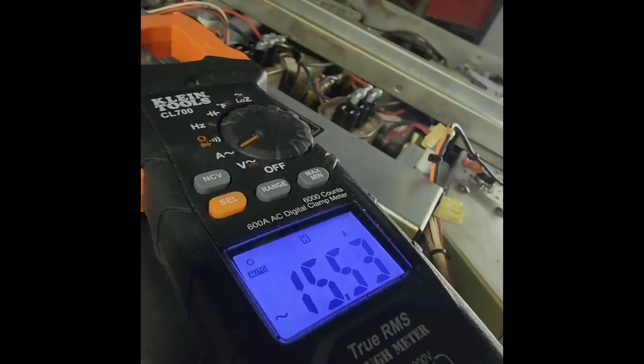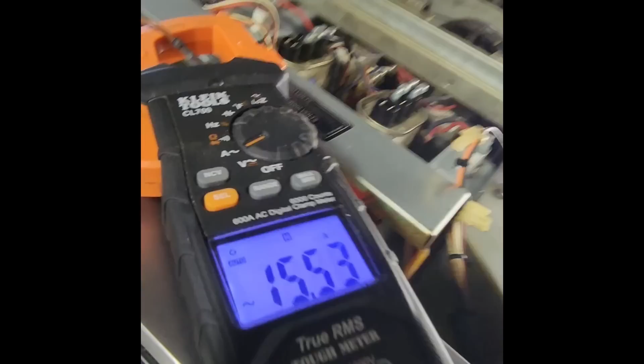Again, I'm doing another cook cycle. Right now it's reading 15.5, but I think I caught that on hold. That's my fault. As you can see on that meter, the H is highlighted, so that means I pressed it too long, so it's holding at that point. So that's not the actual amp draw. I caught it when it was going up in amperage, and I pressed the hold button by mistake. So it's just holding at 15.5, but really it's around 17.5. Usually you'll get 15.5 to 16 amps on the amp draw when you have like 240 volts going in, but this only has 208 going in, so my amp draw is going to be a little higher.